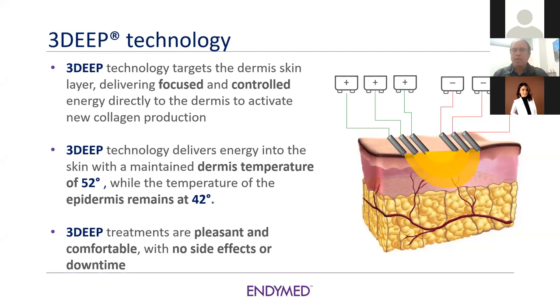The simultaneous multiple electrode fields created by the multiple sources repel or attract each other, leading to three-dimensional delivery of RF energy to the dermis and subdermal targets, minimizing the energy flow through the epidermis without the need for active cooling. The combination of the controlled phases of the 3D energy delivered to different electrodes and the configuration of the electrodes allows concentrating the delivered energy in a specific region below the skin surface at a particularly high efficacy.